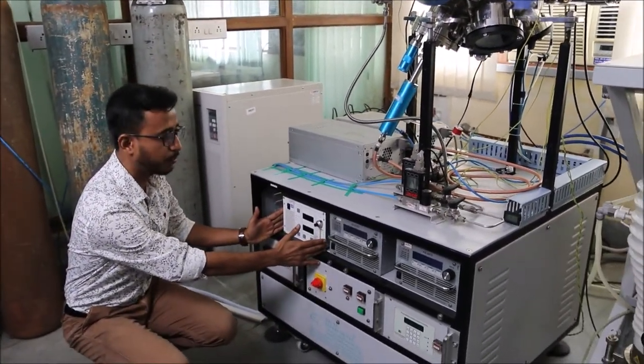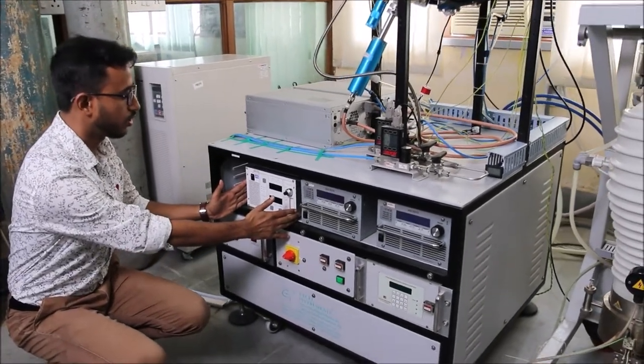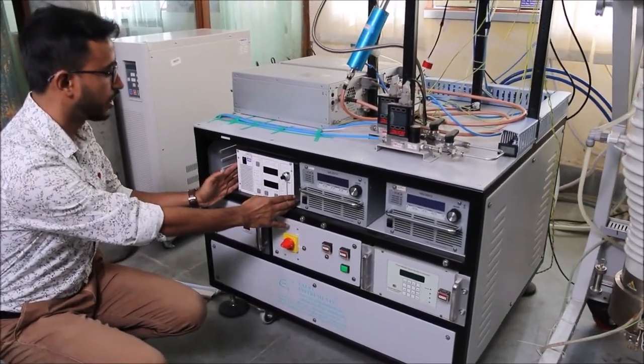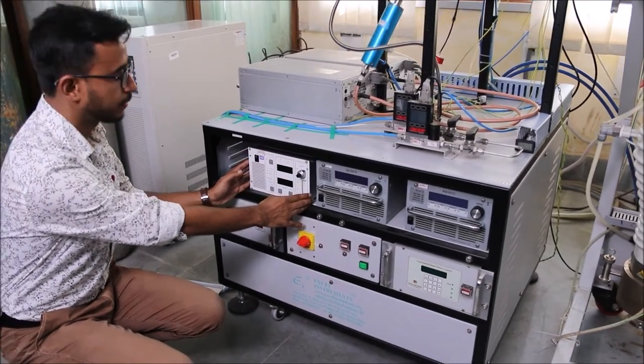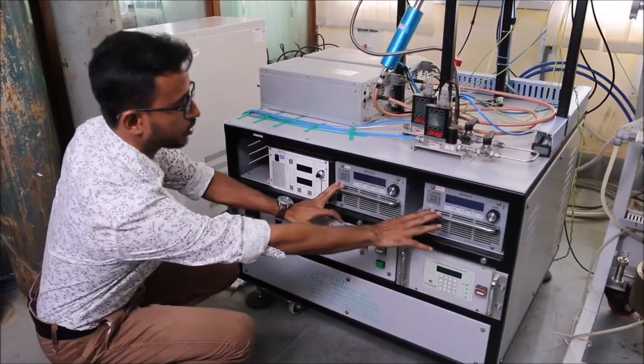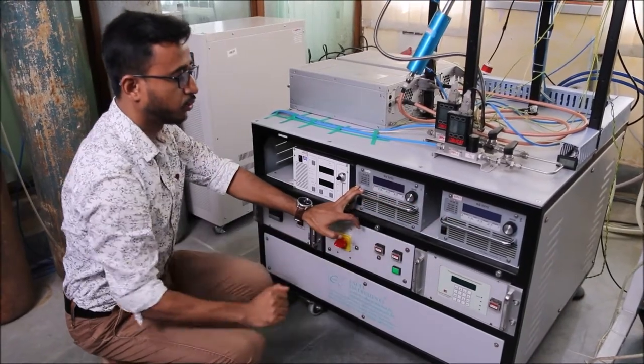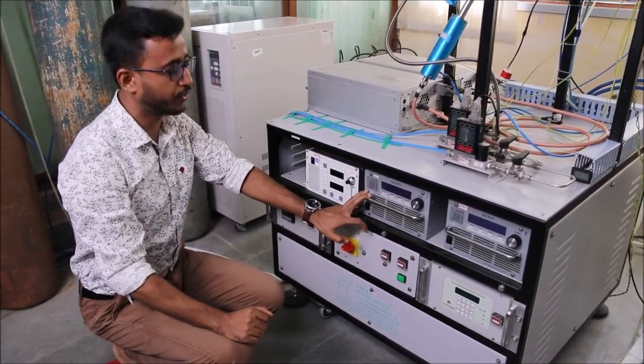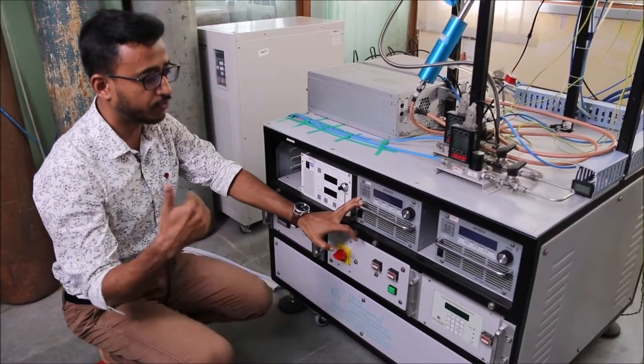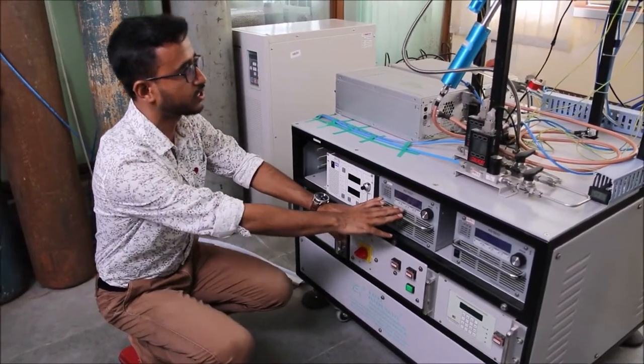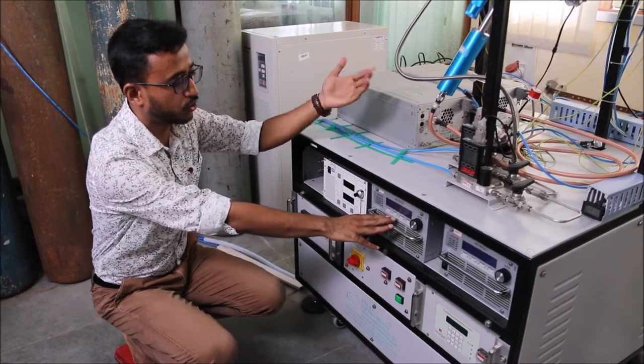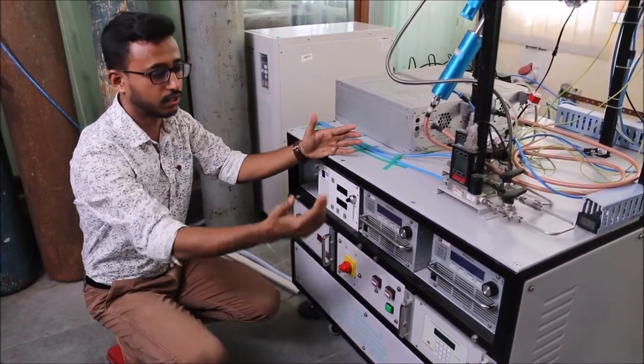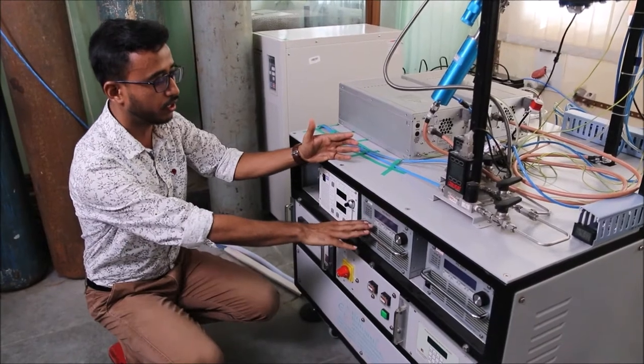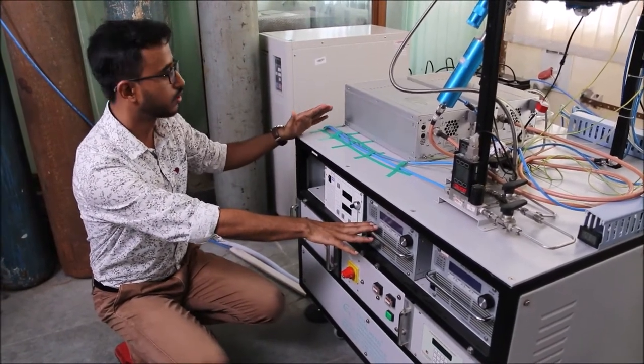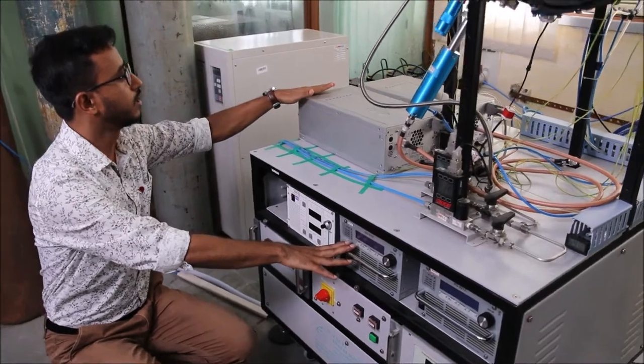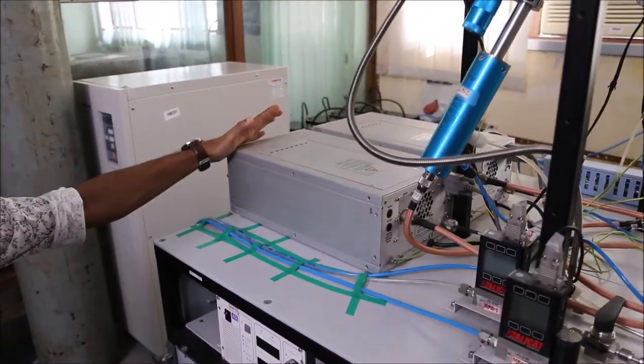So first, this is the DC power source, which is mostly or frequently used for the metal targets. And we have two power sources for RF. We use 13.56 megahertz of frequency, and because at that frequency the power cannot be directly transferred to the output or to the load because of the mismatch of the impedances, we need to connect a matching network. So this is placed at this part. So we have two matching networks for these two RF sources.